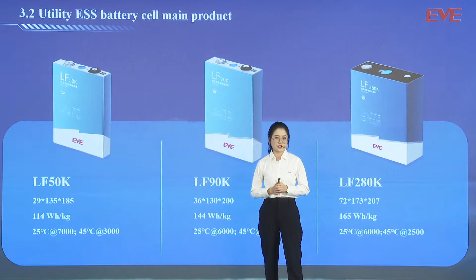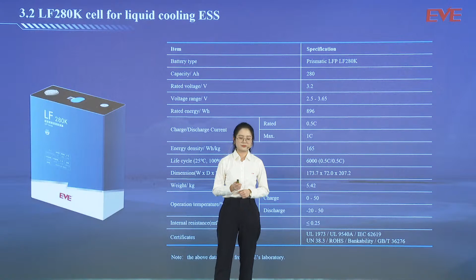This is our LF280K cell, EVE's star product for the utility ESS, which has a large capacity of 280 ampere-hour and a high cycle life of 6,000 cycles, with a maximum 1C charge and discharge rate. Currently, it has obtained relevant domestic and foreign certifications such as UL 1973, UL 9540, IEC 62619, UN 38.3, RoHS, bankability, GB/T 36276, etc. At the same time, it is also the cell used for our liquid cooling system.